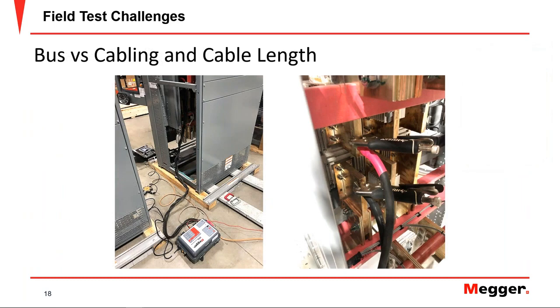Next is the decision between using bus or cabling for my connections from the SPI to the breaker under test, right? Either can be utilized. The current will be the main requirement that will dictate the best application for either option. Because this presentation is focused on low voltage circuit breakers, with currents up to 2,000 amps, you can say the cables are the preferred method because of the flexibility and ease of connection. The length is of equal importance to the thickness of the conductors we use, right? We want to minimize the total impedance of the circuit we are connecting to the SPI, as this will obviously impact how much current we can get out of the unit in that particular configuration.